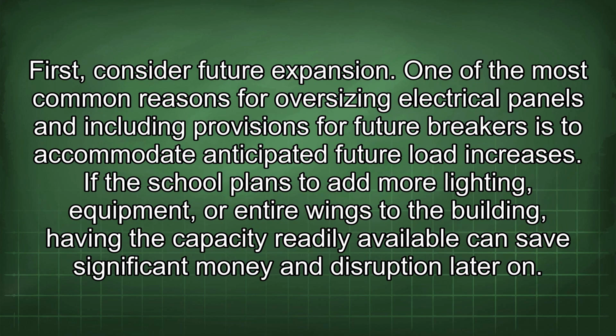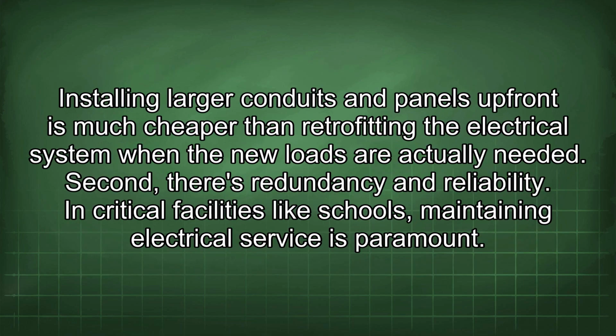First, consider future expansion. One of the most common reasons for oversizing electrical panels and including provisions for future breakers is to accommodate anticipated future load increases. If the school plans to add more lighting equipment or entire wings to the building, having the capacity readily available can save significant money and disruption later on. Installing larger conduits and panels upfront is much cheaper than retrofitting the electrical system when the new loads are actually needed.